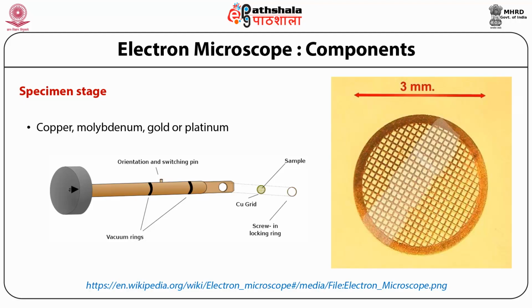The specimen stage looks like this, where we have the vacuum rings. As we know, the inside of the system is vacuum tight, so the sample is put in the grid as shown in this picture, and then these two rings ensure that vacuum is maintained inside. The grid is kept in that stage, and then the stage is pushed in under the microscope, in which the electron beam will directly hit this grid containing the sample.